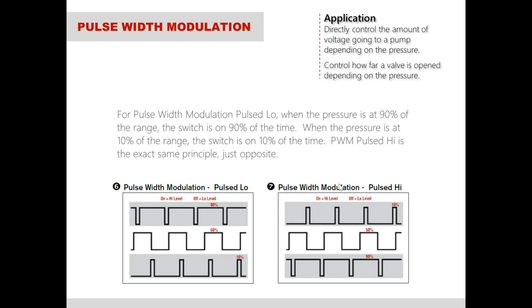And what you can do with this signal is you can send it directly to a pump or a motor or a valve and say, hey, my pressure is at 90%. You need to turn on this pump at 90% of the voltage that it's required to maintain it. And you can say the same for a valve: open a valve up to 90% open. So there's a lot of things that you can do with pulse width modulation, though it's not necessarily one of the more common ways the switch is used.